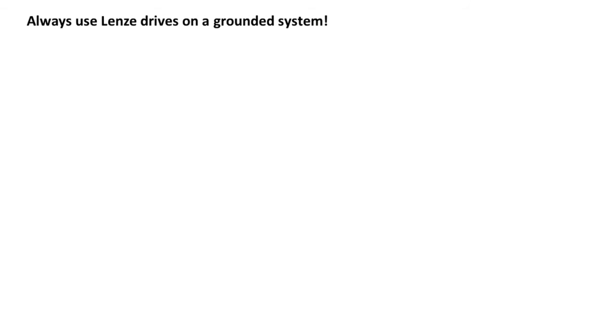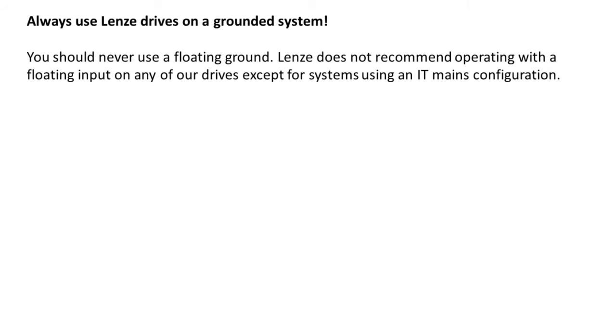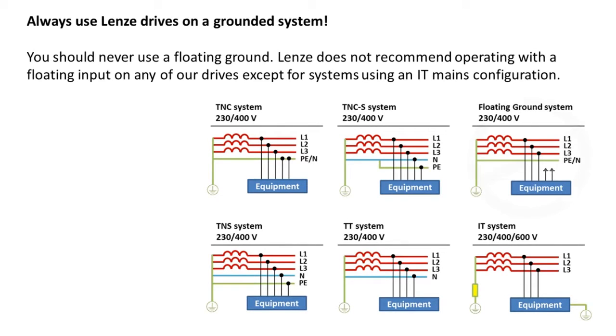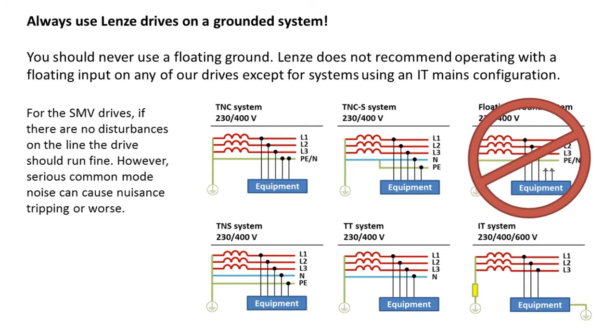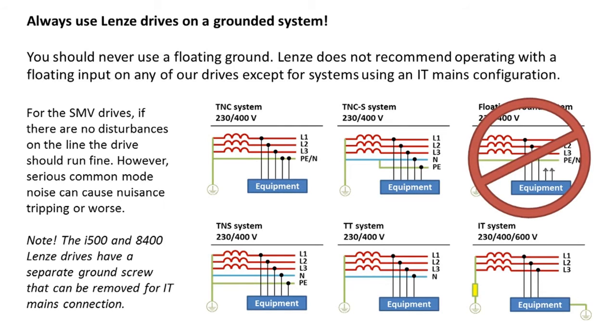Always use our drives on a grounded system. You should never use a floating ground. Lenze does not recommend operating with a floating input on any of our drives except for systems using what's called an IT mains configuration. However, for the SM vector drives, we do not have this IT mains separate connection screw. For the SM vector drives, if there are no disturbances on the line, the drive should run fine. However, serious common mode noise can cause nuisance tripping, so it is important that these restrictions be observed.